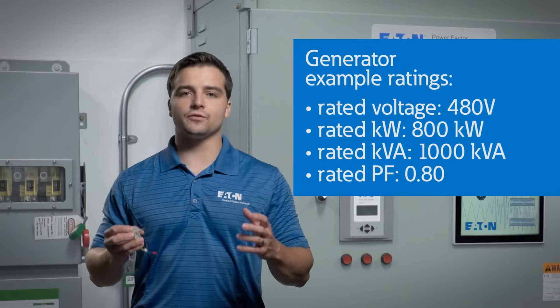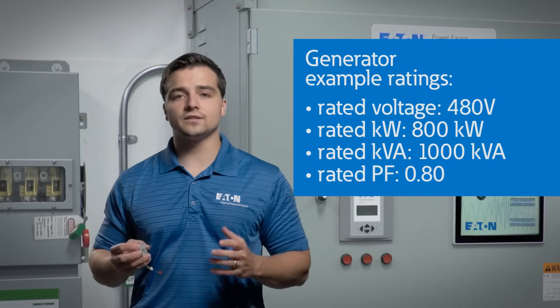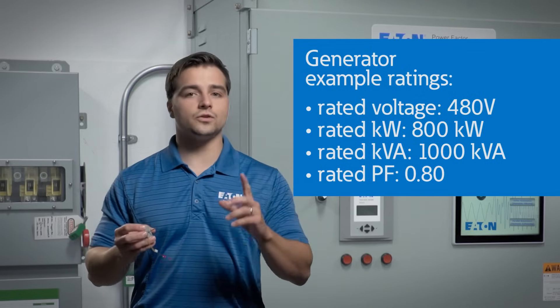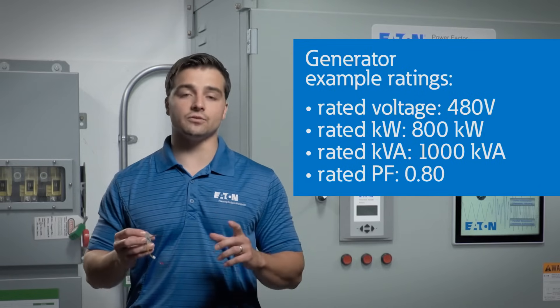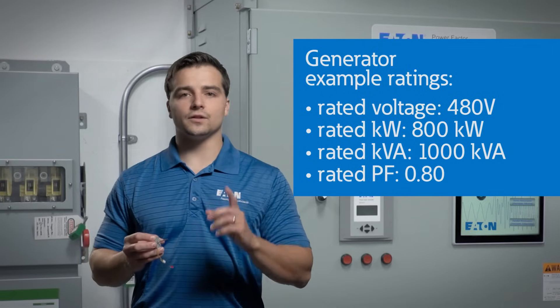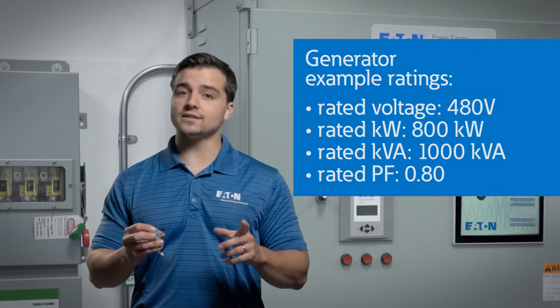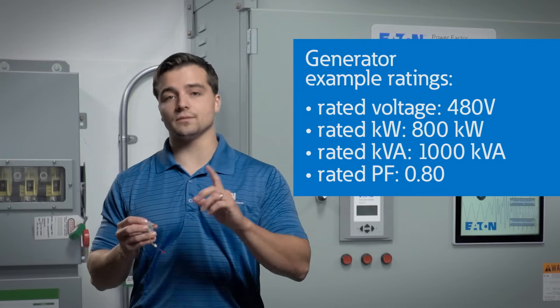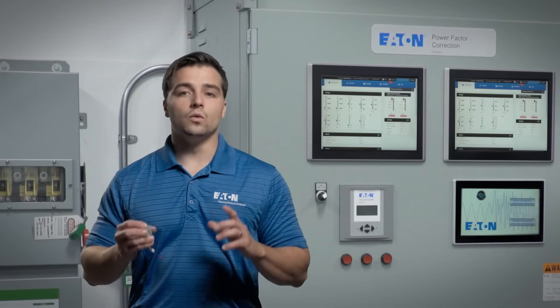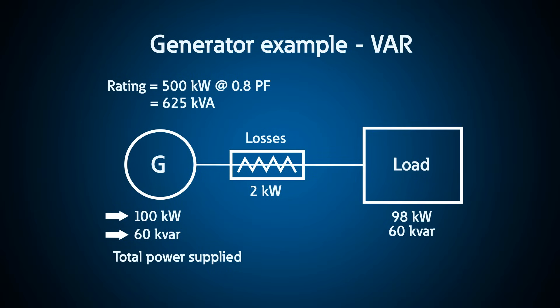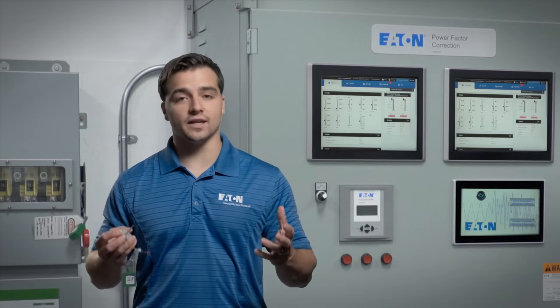Many people just reference the kilowatt rating, but you have to consider both to understand the actual capacity of a generator. Keep in mind that the load is what demands the reactive power that the generator then supplies. Without a load, there is no current, and you just have the open circuit voltage multiplied by a current of zero yielding no power at all. Remember, the armature windings are inductive so they play a role in the overall circuit when a load is connected.